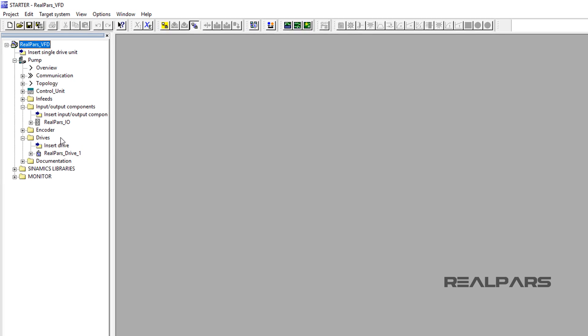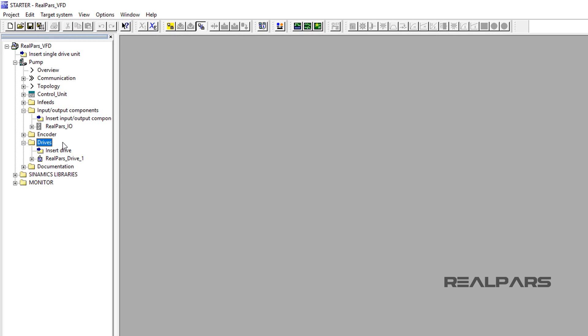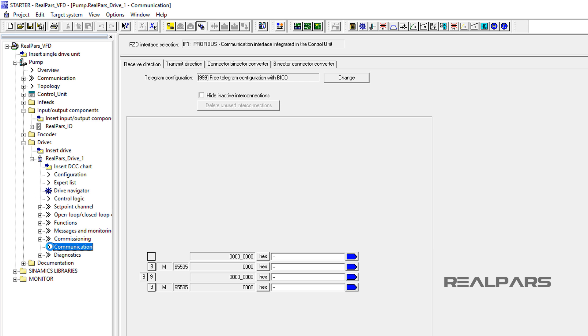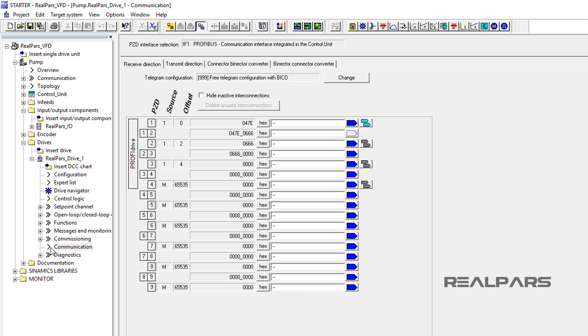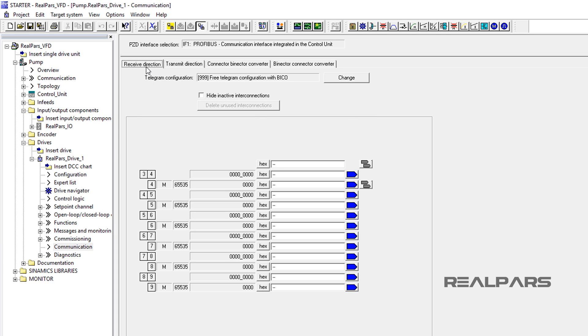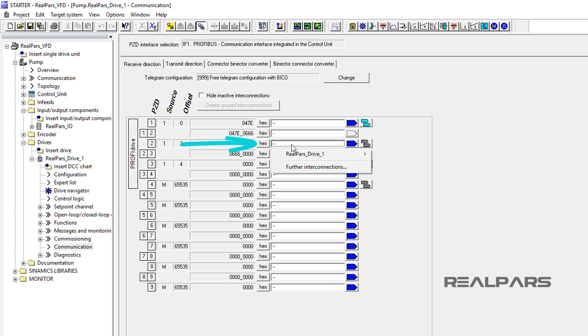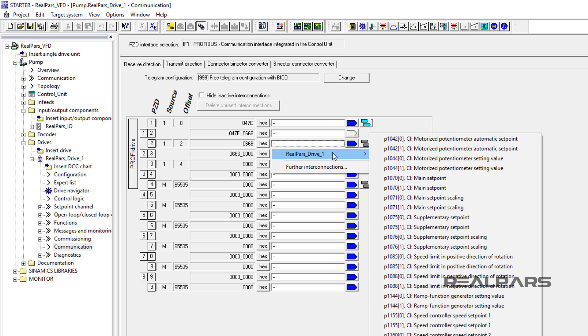Now, under the Drives folder, I expand the RealPars Drive 1, then I double-click on Communication item. Within the Receive Direction tab, I will click into the PZD2 and click in the white area next to the hex box. Then I open the RealPars Drive 1 menu to select P1070-0, the main setpoint.